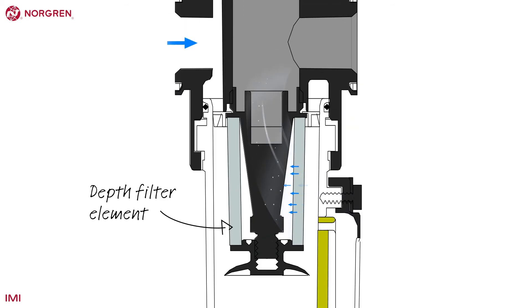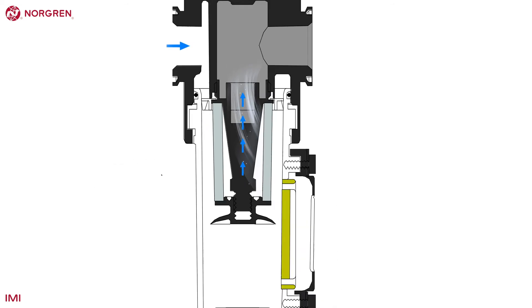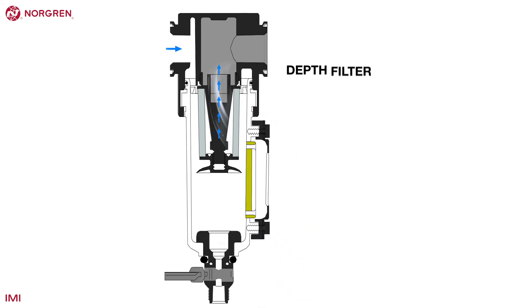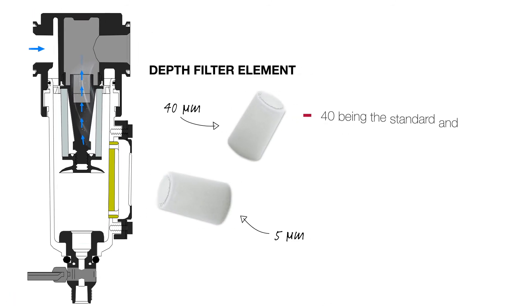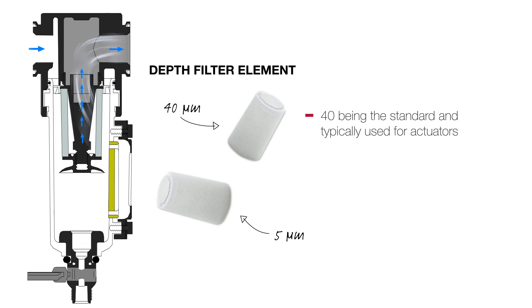The air is now directed through the depth filter element that not only stops particles but long strands too. Filter elements are rated on their micron size — this is the size of particle it will stop. The two options that Norgren offer are 40 micron and 5 micron, with 40 being the standard and typically used for actuators. 5 micron is usually specified to protect more sensitive parts like a proportional valve. The filtered air then leaves through the outlet to carry on downstream.